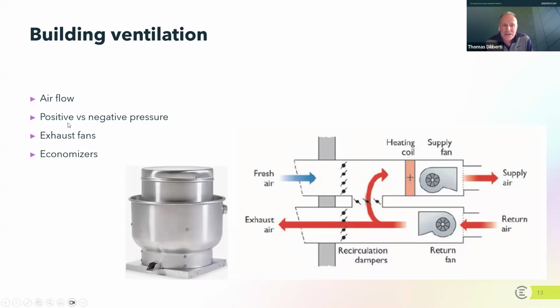Buildings can either be positively or negatively pressured. Most buildings, when optimally designed and operated, have a slight positive pressure, which resists the intrusion of outside air. You may have had the experience of walking up to the front door of a bank or mall where you try to pull the door and it resists you, or it flies open easily. Usually pulling the front door gives you a sense of whether a building is positively or negatively pressured. If it comes out easily, it's positively pressured. If the door sucks in and resists being pulled, that's a negatively pressured building. You want a building that's slightly positively pressured. So if you're evaluating your buildings, this is something you can often observe right away, and you should identify any buildings that are negatively pressured, because usually there are other problems associated with it.